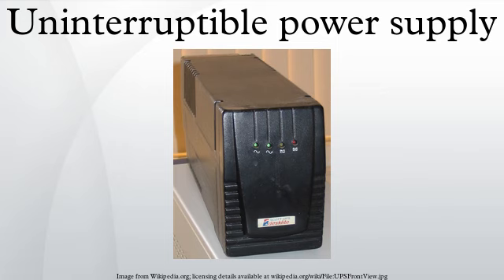These issues also apply to other situations where series parallel strings are used, not just in UPS systems but also in electric vehicle applications. Consider a series parallel battery arrangement with all good cells, and one becomes shorted or dead. The failed cell will reduce the maximum developed voltage for the entire series string it is within. Other series strings wired in parallel with the degraded string will now discharge through the degraded string until their voltage matches the voltage of the degraded string, potentially overcharging and leading to electrolyte boiling and outgassing from the remaining good cells in the degraded string.